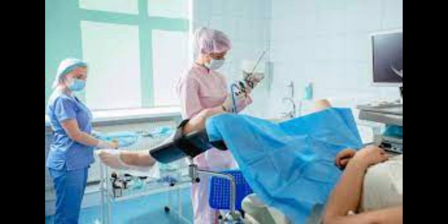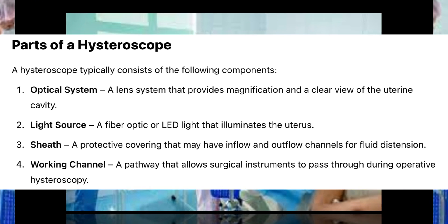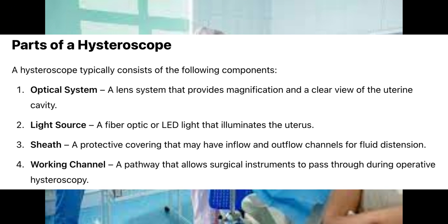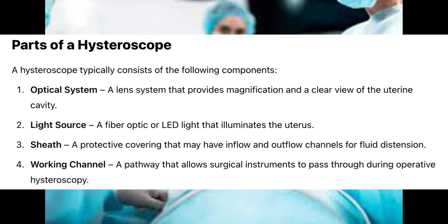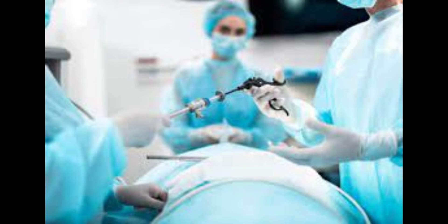Parts of a hysteroscope. A hysteroscope typically consists of the following components: 1. Optical system — a lens system that provides magnification and a clear view of the uterine cavity. 2. Light source — a fiber optic or LED light that illuminates the uterus. 3. Sheath — a protective covering that may have inflow and outflow channels for fluid distension. 4. Working channel — a pathway that allows surgical instruments to pass through during operative hysteroscopy.